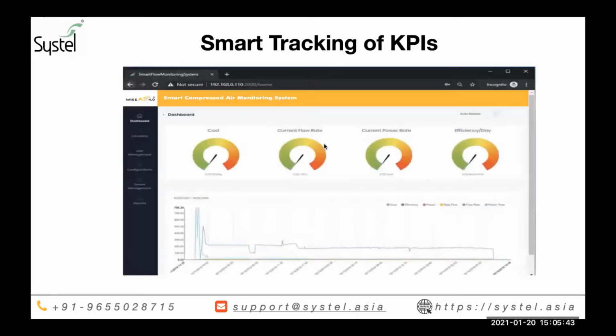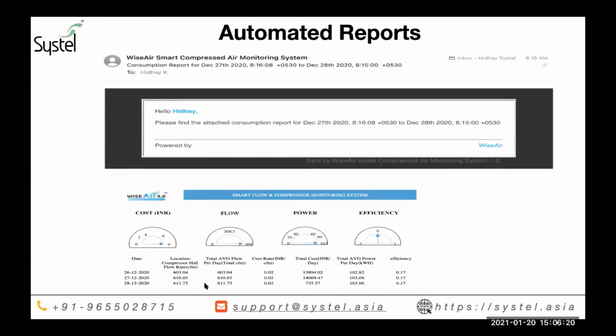Overall, with all the data and information collected from various sensors, the software provides you a dashboard and a snapshot view of the cost you're incurring for generating your compressed air, what your system efficiency is, what the power rate is, and you get all the trending graphs in real time. And another thing is you can have threshold levels defined in the software. Whenever the consumption exceeds your threshold levels, you get a user alert. You can also assign automated reports wherein you get quick information about the overall efficiency level of your system.